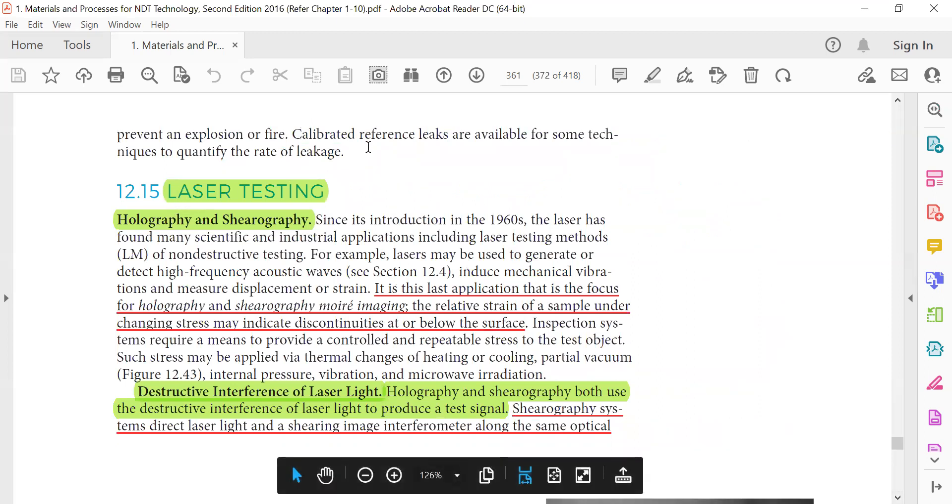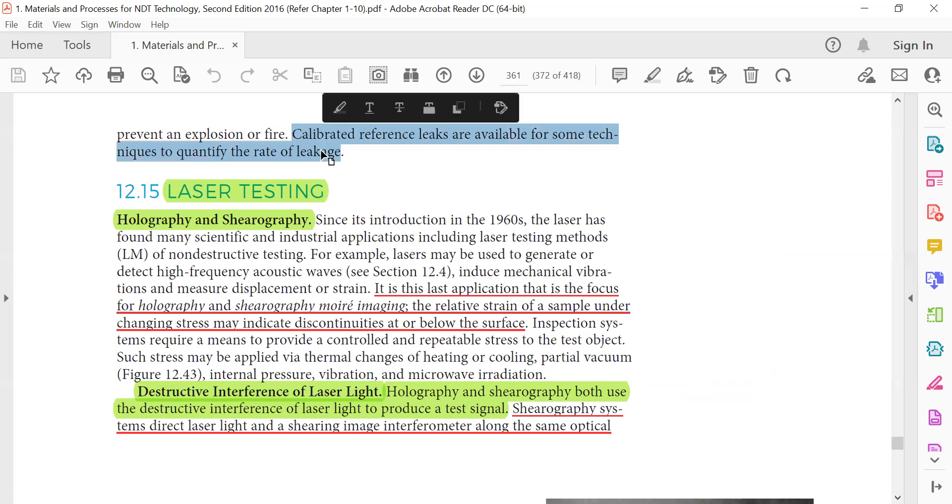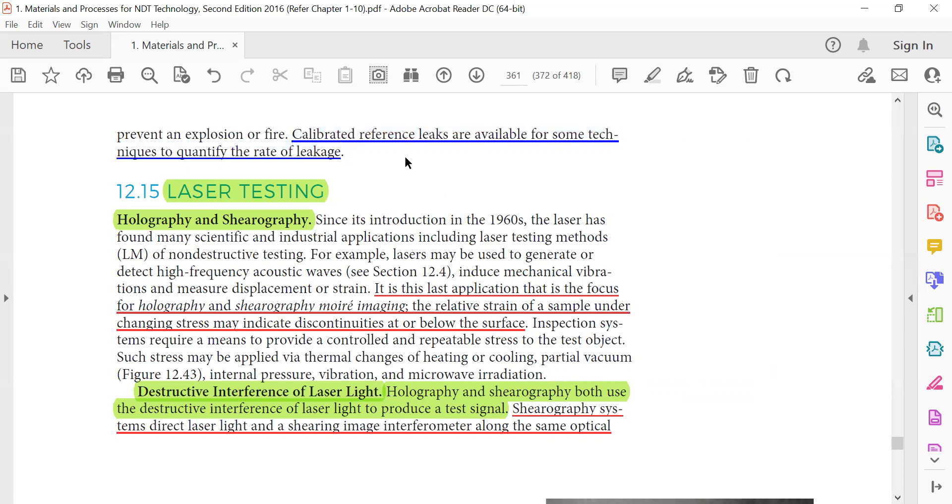Calibrated reference leaks are available for some techniques to quantify the rate of leakage, so that you can compare with those reference standards.